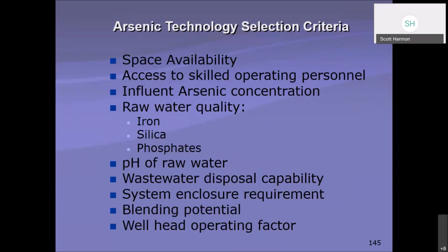Blending potential. I think that was on the first slide. Is there a way that we can blend our water so that we are within range without even having to treat for it? The wellhead operating factor, we talked about that earlier too. Is it a possibility that we can operate our wells differently? Can we get into a lower aquifer? Can we screen off some portion of the aquifer that has higher arsenic levels in it? So these are some factors.